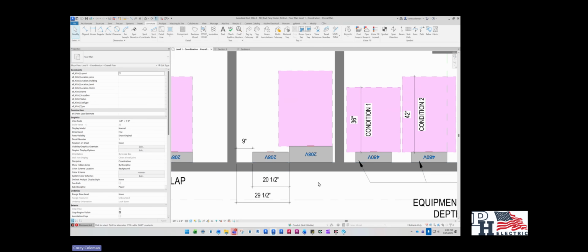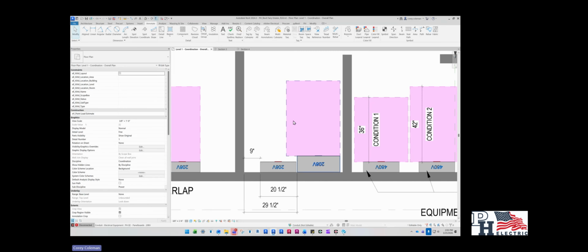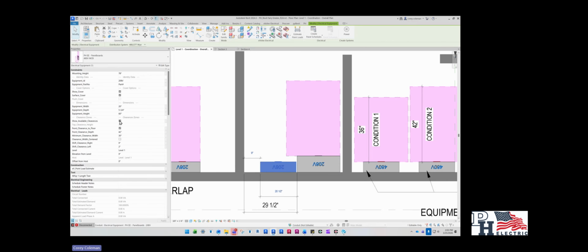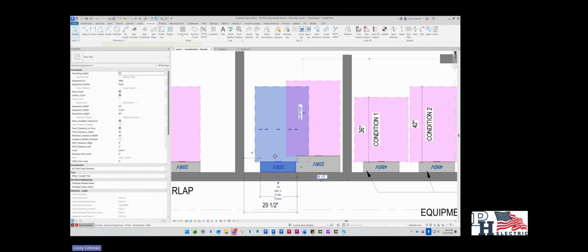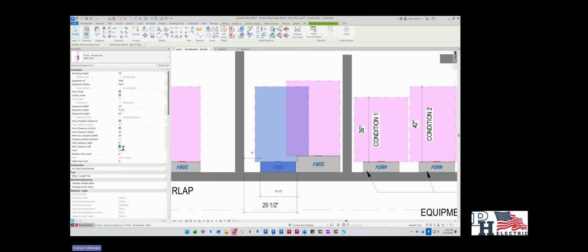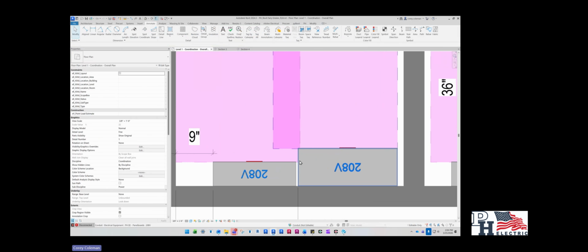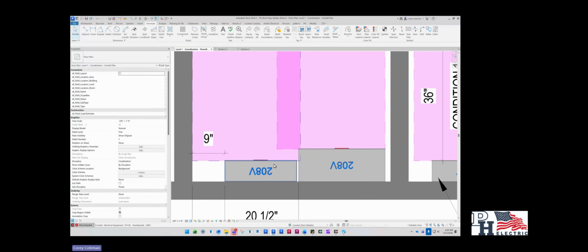Little quiz here: if I have a panel side by side and I'm going to use the left edge of this panel to justify it, do I have enough clearance space for this panel? The answer for this one is going to be no, because even if I justify the clearance to the left all the way, let's go 6 inches, it's still going to be butting into the other panel itself. And you can see that we're actually into that panel, so this actually isn't clear enough.